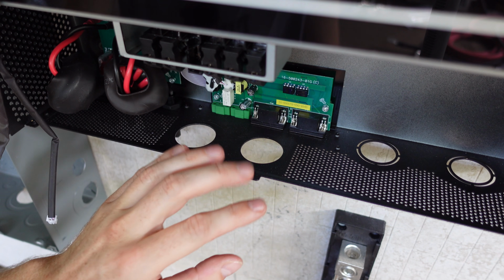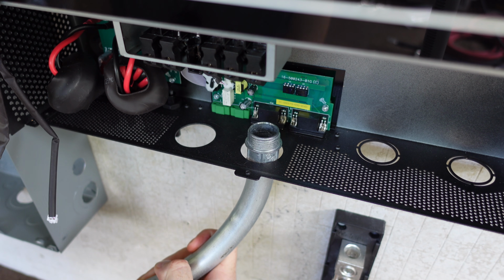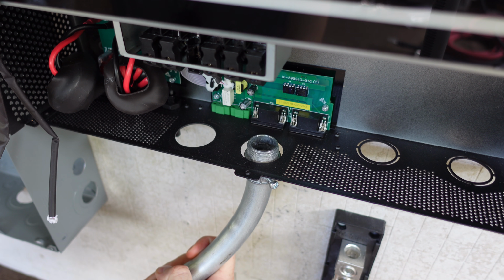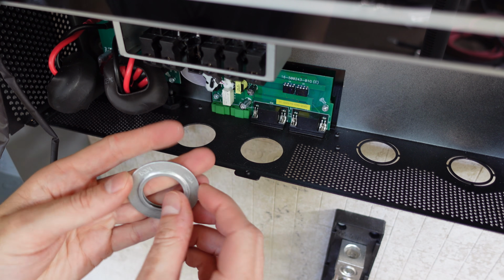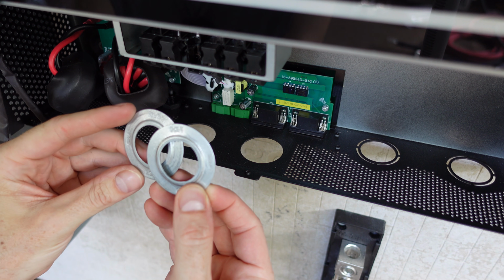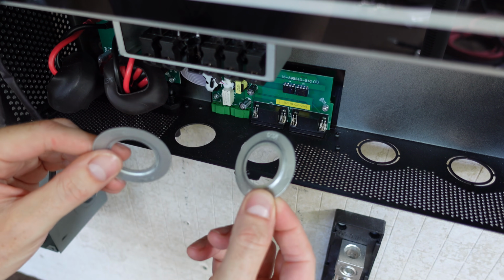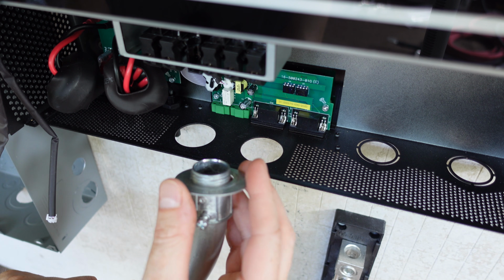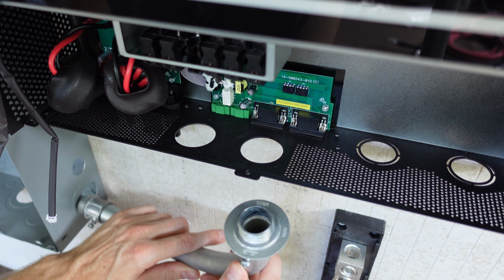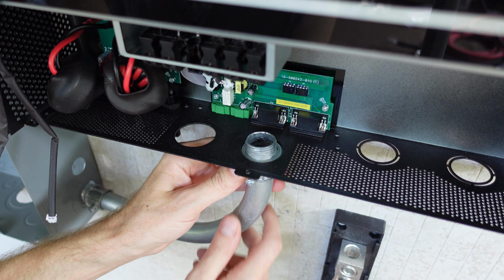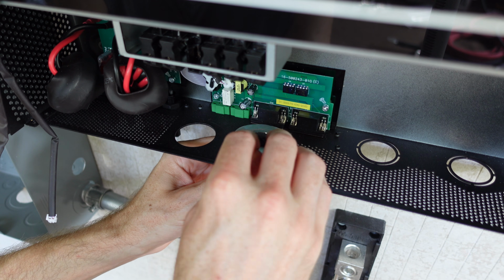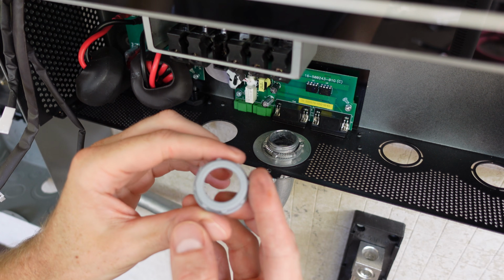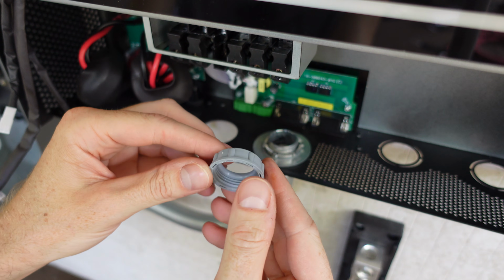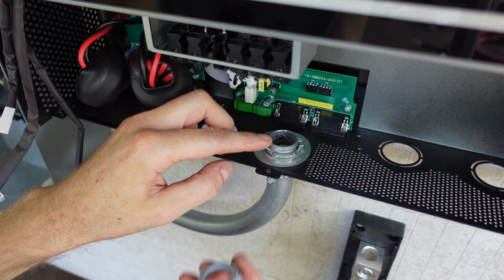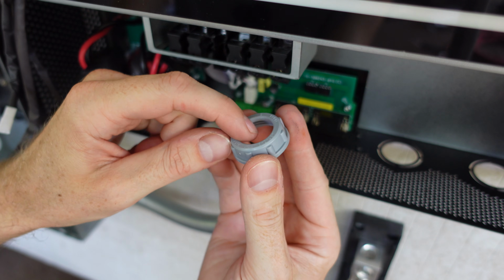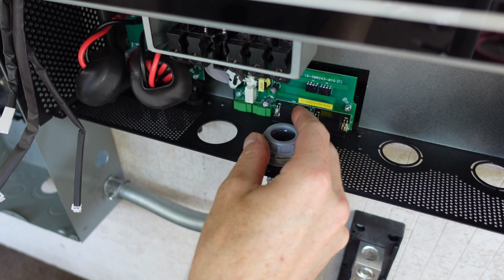Now, the holes in the bottom of this inverter are quite large. You can see how large they are in comparison to this conduit piece. So the hardware store sells these little adapter plates. This is a 1 inch to a 3/4 inch adapter. I'm going to place one of these on the bottom of the conduit fitting, and then a second one of these goes on the top of the conduit fitting. And then I've got these little plastic bushings here which sit on top of the conduit fitting, and they just provide a smooth surface to pull your wire through.